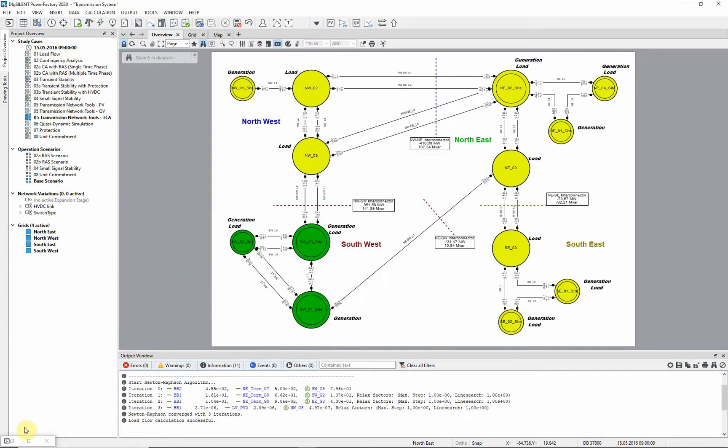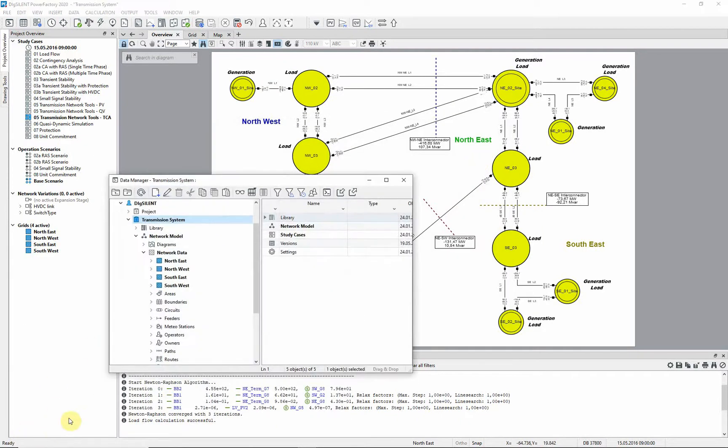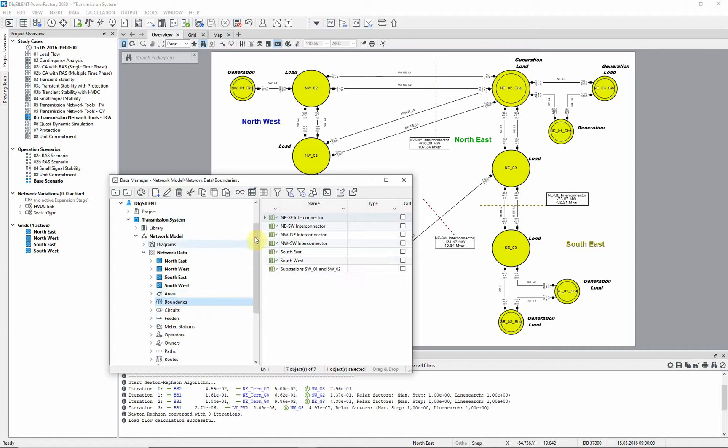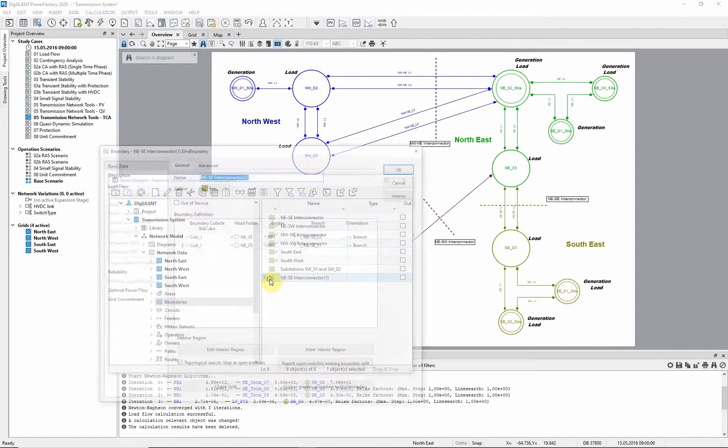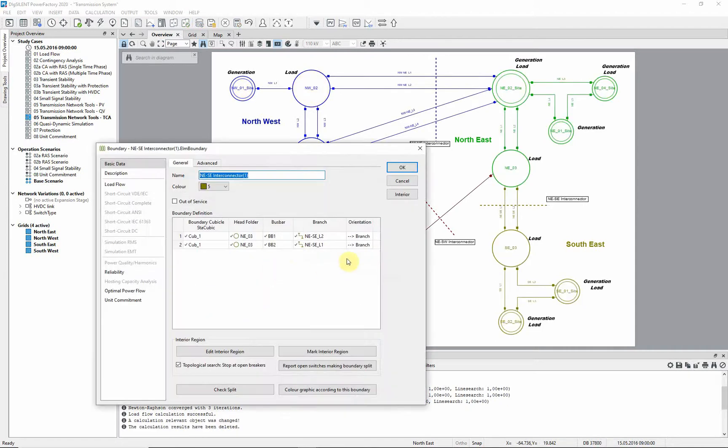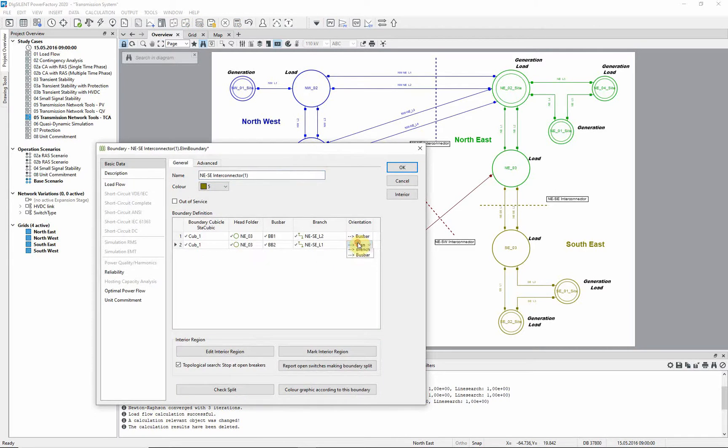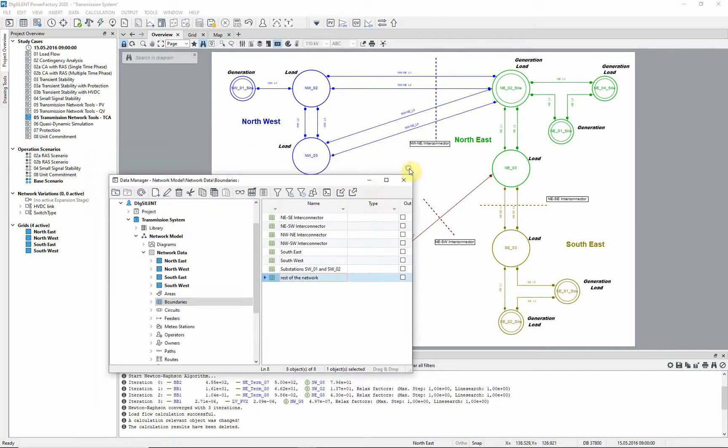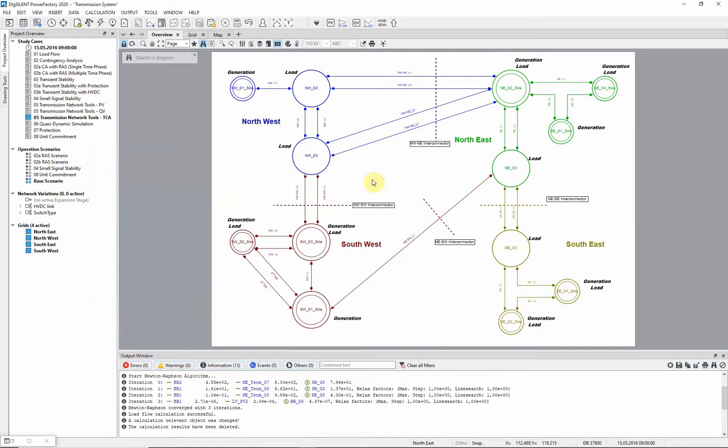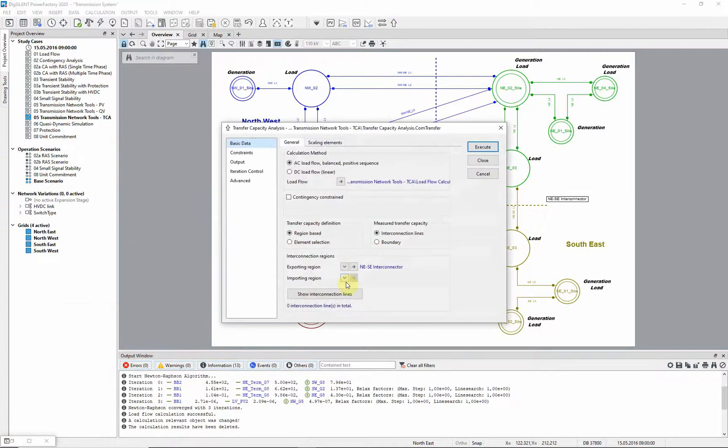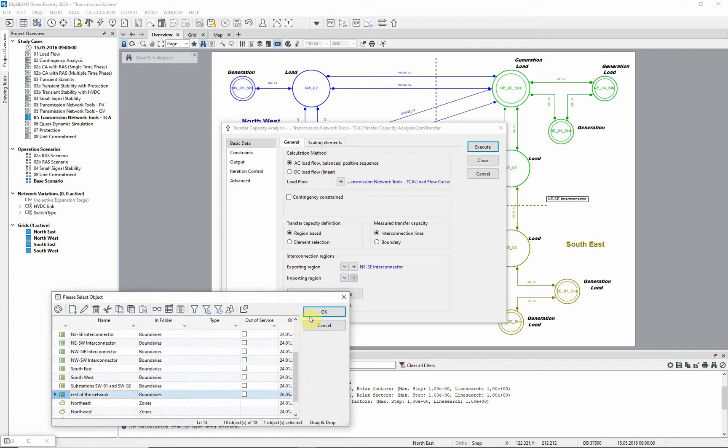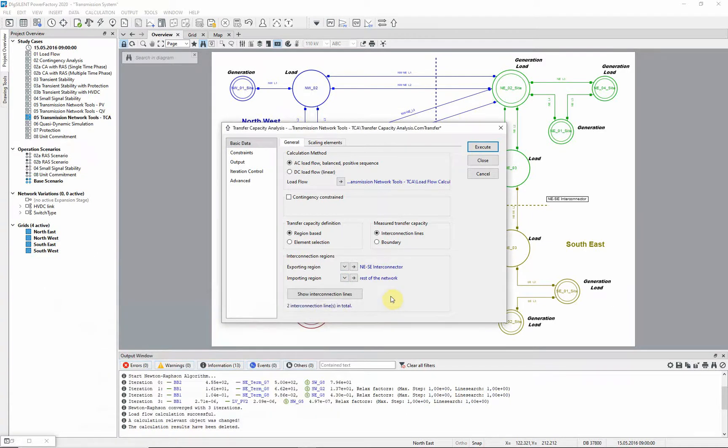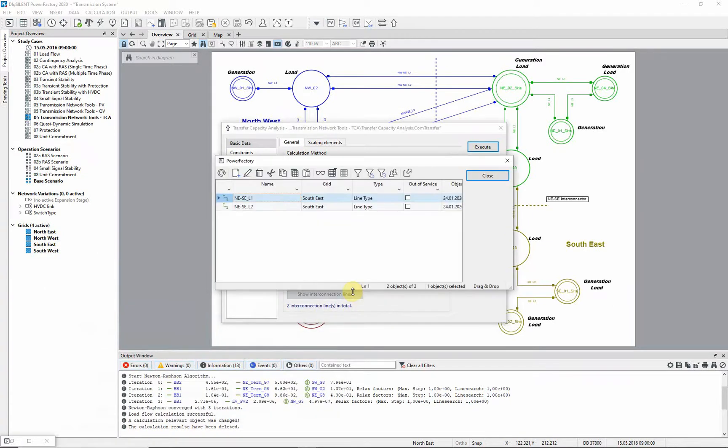The importing region will be the rest of the network. To define a boundary for this, we can simply copy the NE-SE boundary in a data manager and reverse it. Returning to the transfer capacity analysis dialog, this new boundary is selected as the importing region. Notice how the two interconnecting lines are automatically identified.